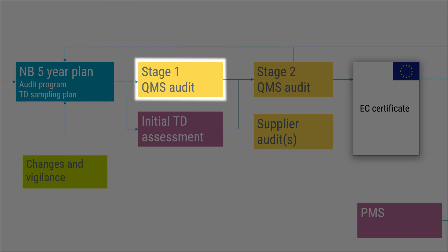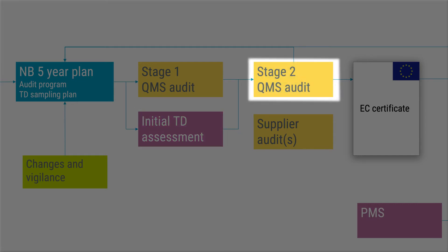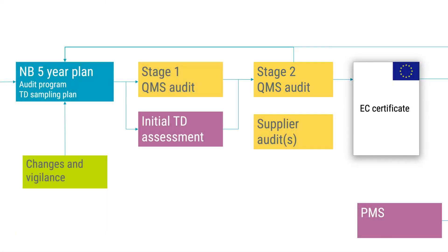The initial QMS audit is composed of a stage one audit where the notified body ensures that the manufacturer's QMS covers all applicable requirements of the MDR. The stage one audit duration is typically around 30 percent of the complete initial audit time. Based on the output of the stage one audit, the notified body decides when the stage two, or certification audit, can be conducted. But before the stage two audit is performed, the initial technical documentation assessment shall be reported to the client and also form input to the stage two audit.